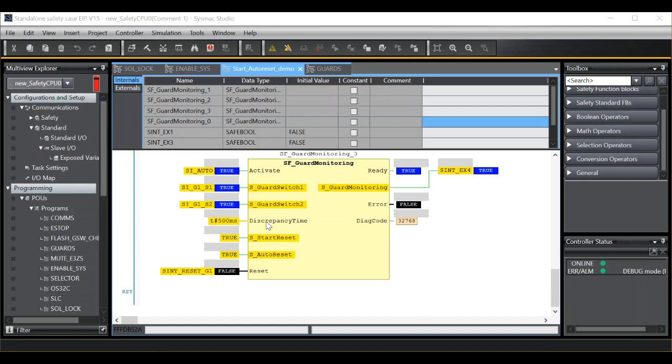If I activate the function block, you'll see that the output transitions immediately to true. Open the guard, obviously moves to false, close the guard, back to true. So the function block is running in a permanent auto reset condition.